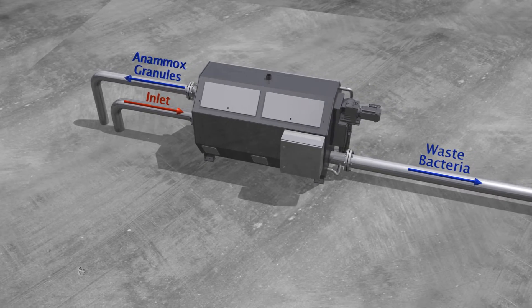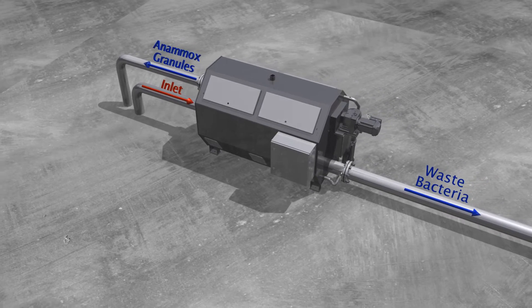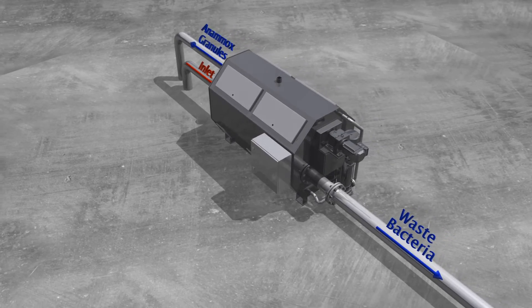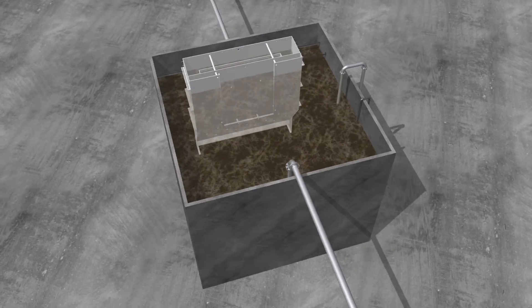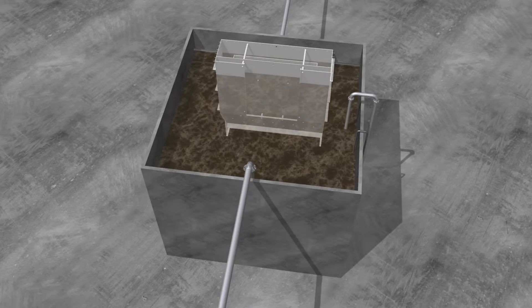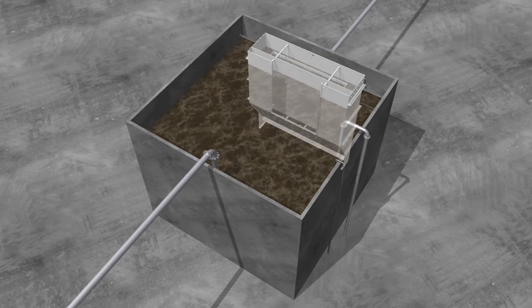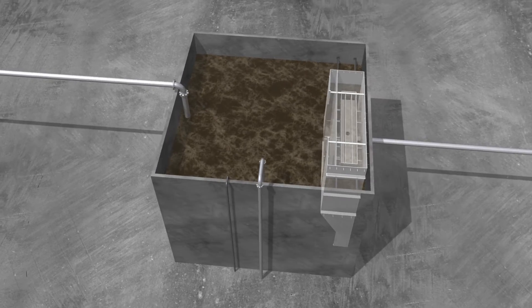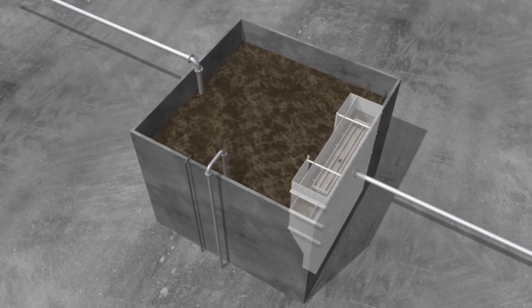granules will go back into the reactor while the waste bacteria will be sent to solids processing. In addition to the micro screen is an internal settling zone which allows the heavier sludge to settle and be reintroduced back into the reactor via gravity, and the cleaner effluent to leave the reactor and be sent back to the front of the plant.